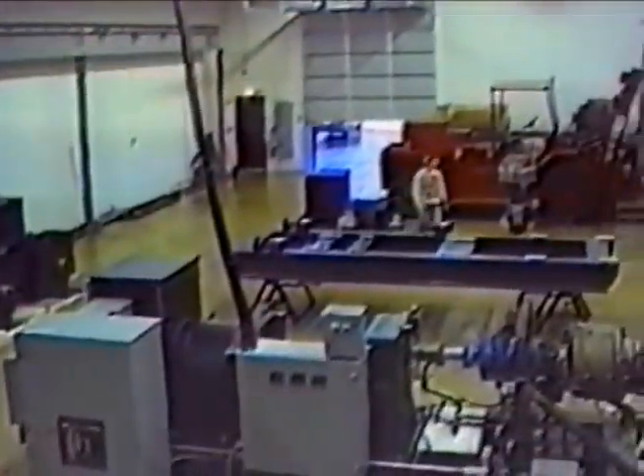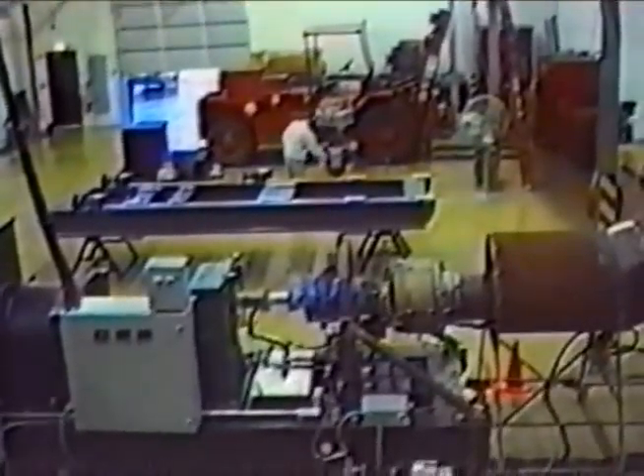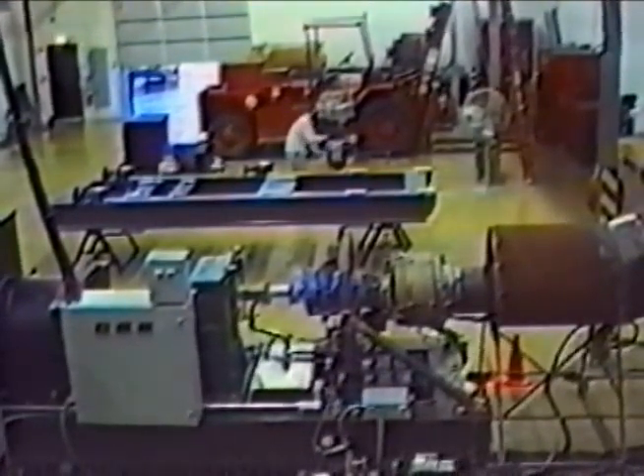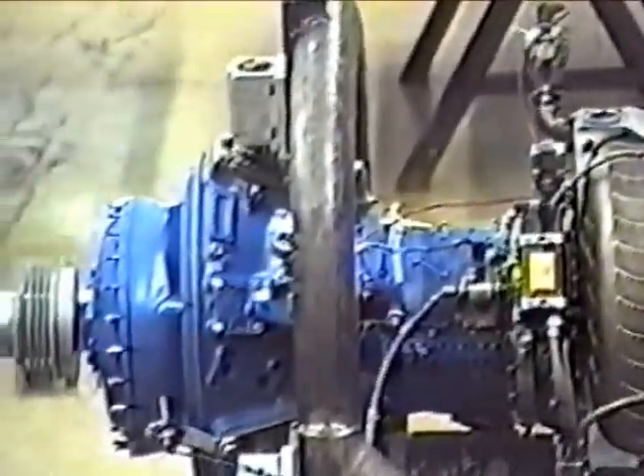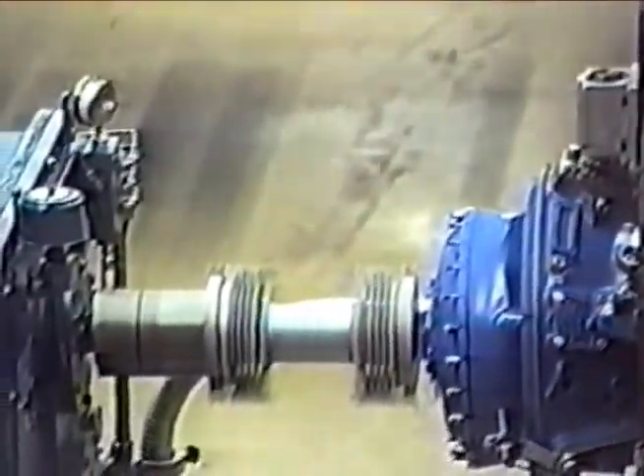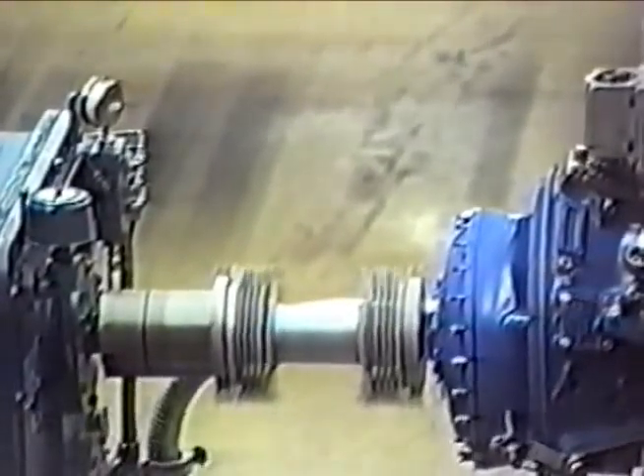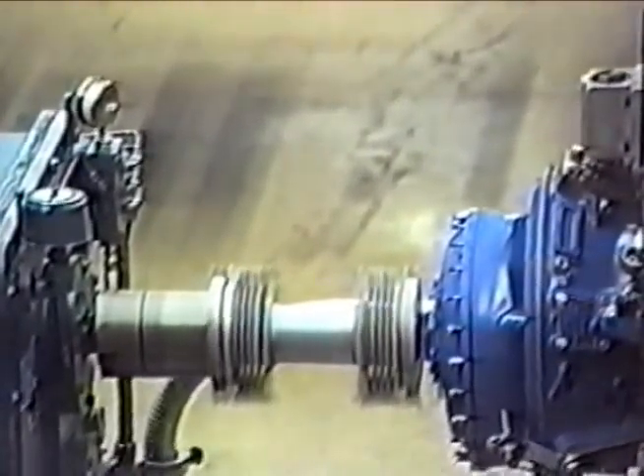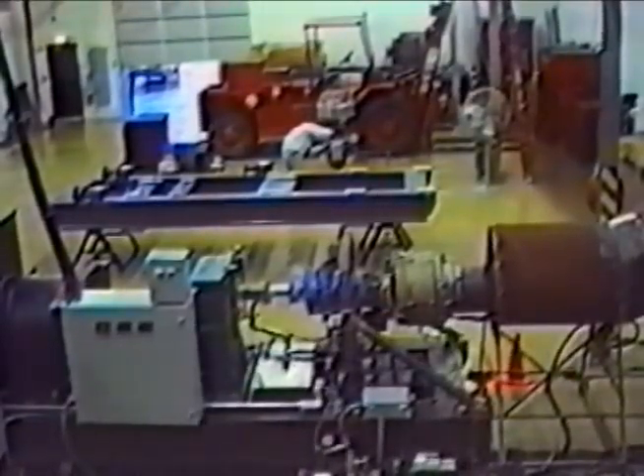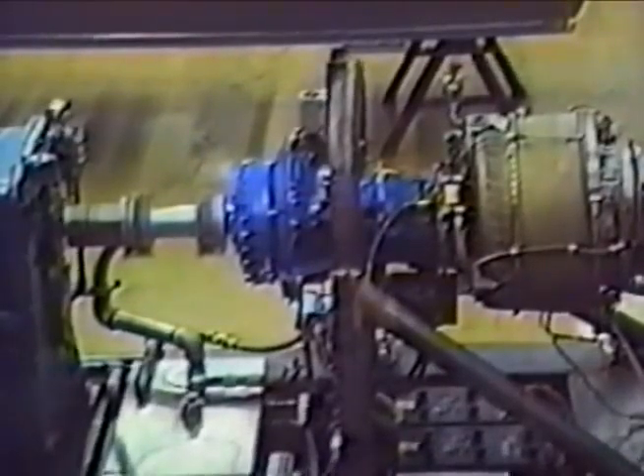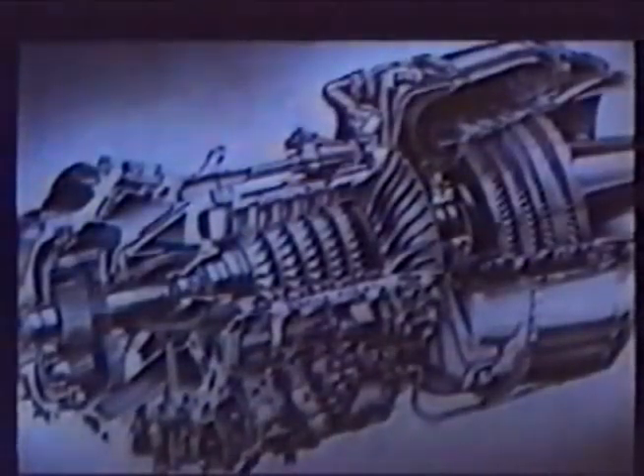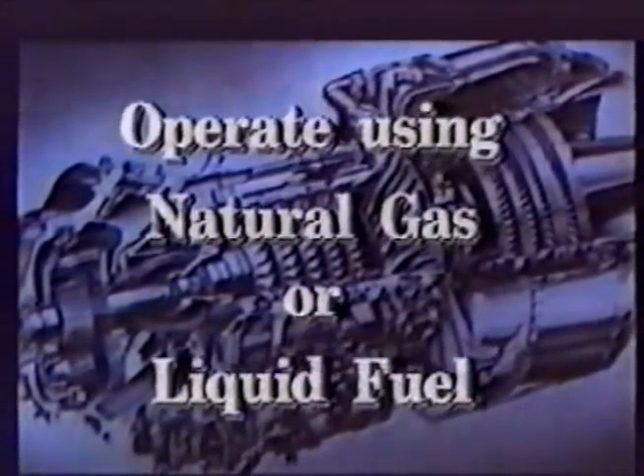The Innovator utilizes highly modified and overhauled Allied Signal-Lycoming T53 gas turbine engines with a shaft output of 6,300 RPM at 1,450 plus shaft horsepower and more than 40 million hours of operational history. These engines were designed for operations under extreme conditions of ambient temperature, severe torque changes, harsh environment, and high cycle counts, which are characteristic of the average aeroderivative applications. These engines have been modified to operate using either natural gas or liquid fuel.